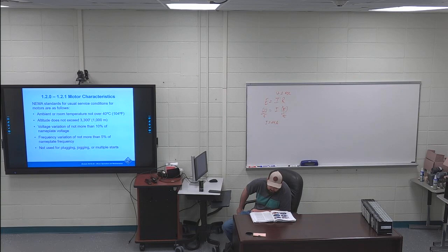Operations outside these limits are a voltage imbalance. So you can have a voltage variation of 10%, but the imbalance can only be 5%. Can result in overheating or loss of torque and may require the use of a larger motor. So 10% variation, 5% imbalance. Two different things there. Make sure you got them differentiated or just separated in your head. Next bullet point is highlighted.